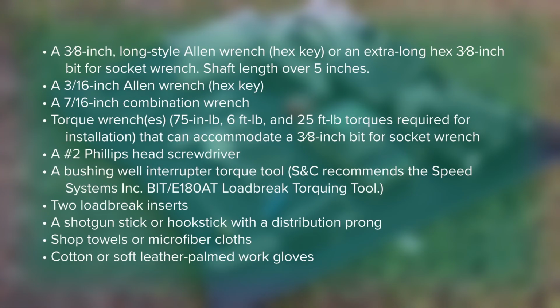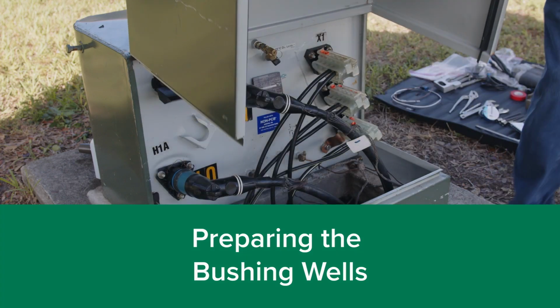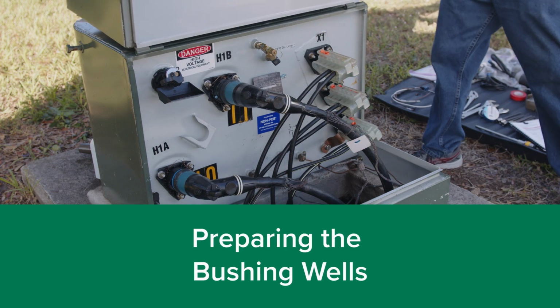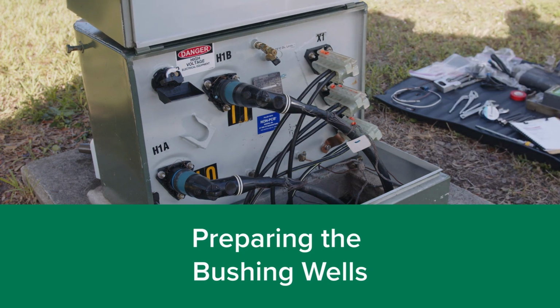In addition to the contents of the installation kit, the following tools, supplies, and parts are required. Note: a long style or long reach bit for a socket wrench is recommended. T-handled or L-handled Allen wrenches may not properly clear the top of the bushing well interrupter during installation. Follow these steps to prepare the bushing wells and install the parking stand link bracket.